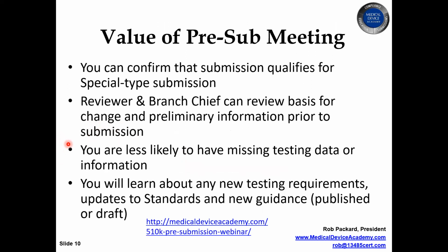And if you're not eligible for a special type, they'll tell you why. Another thing that happens during the pre-sub meetings is it's not just the lead reviewer that's present, but usually the branch chief is also present.